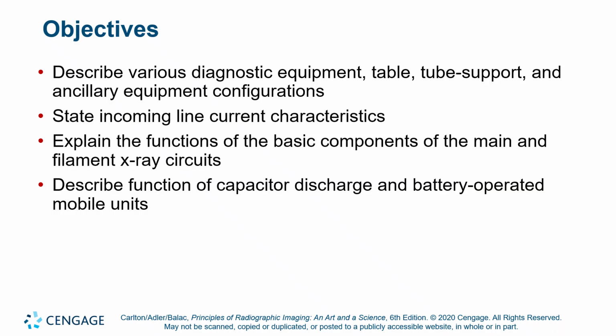We did like one slide at the end of the transformer and rectifier lecture to show you the illustration of the entire schematic and kind of draw the boundary lines in between the control console, which is also the low voltage circuit, the filament circuit, and the high voltage circuit. And so we'll reiterate those points again. And then lastly, talking about either battery operated or capacitor discharge mobile units.